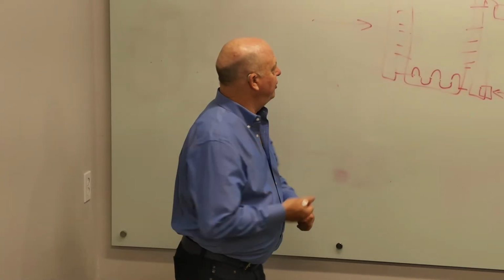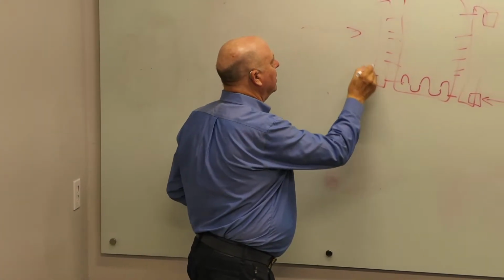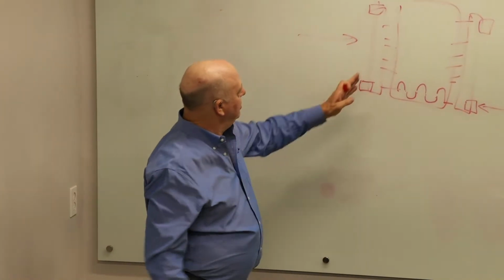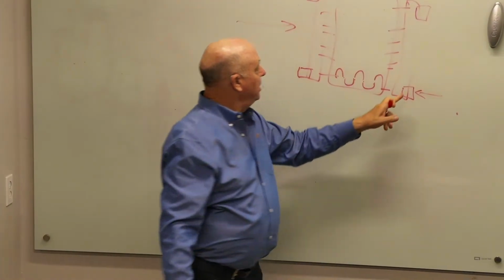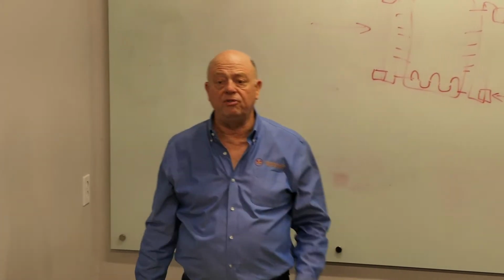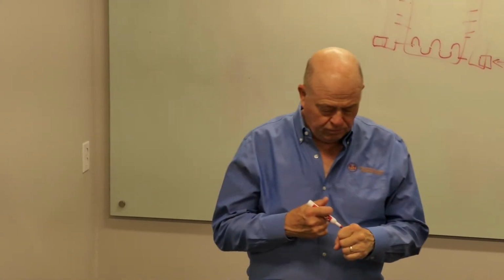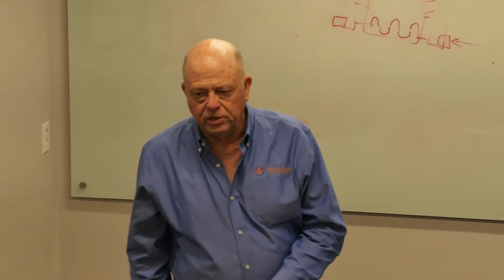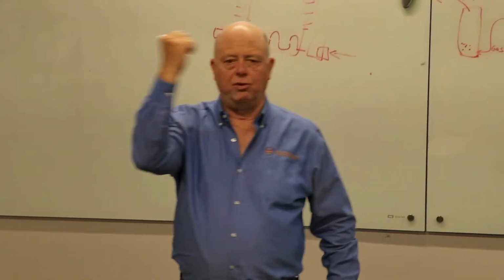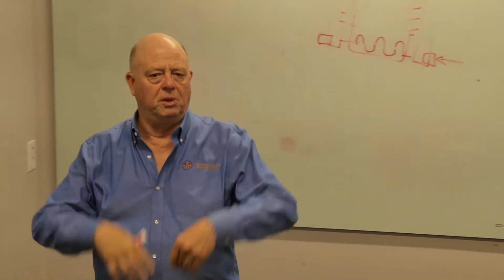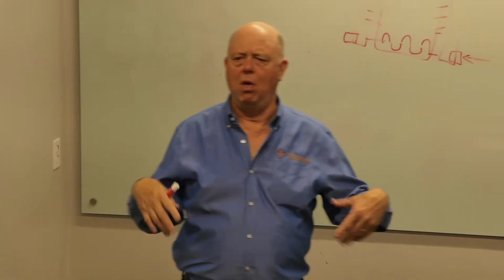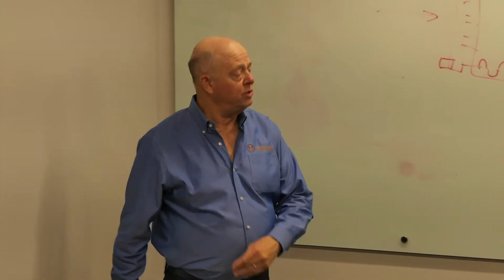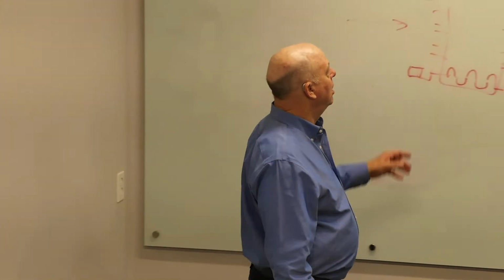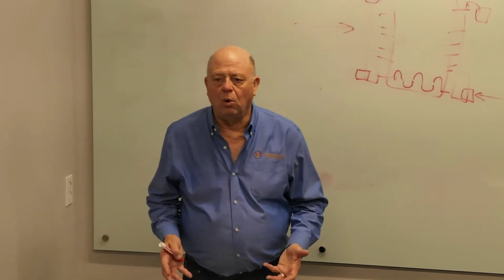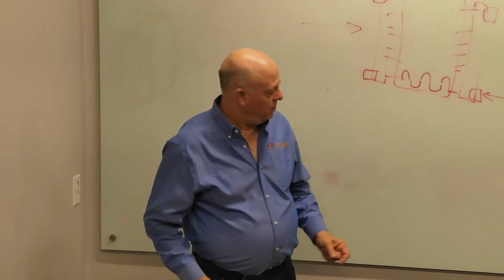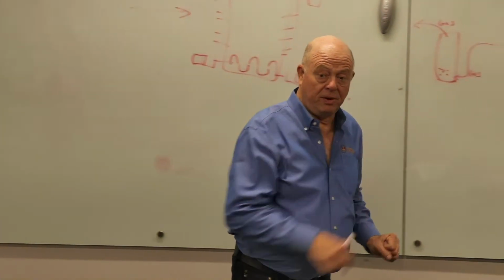So when the guy shows up to pipe the air handling unit, he's going to run into something. Usually these headers are over on the end. But he's going to have 1, 2, 3, 4 potential connections. The old wives' tale was the water goes in the bottom and out the top, and that keeps you from accumulating air. You will find pipe fitters today who believe that. That's not the goal. The goal is to pipe it counterflow.